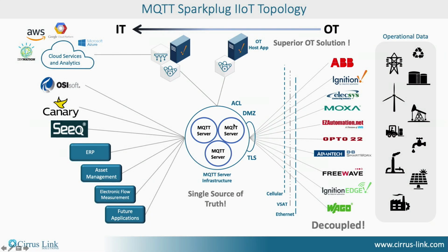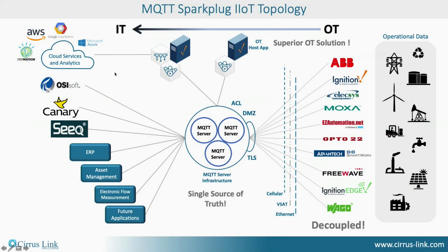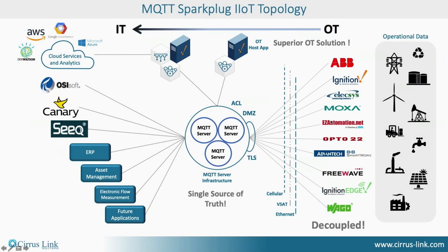You don't care, well, you do care, but if your HART transmitter dies, the edge of network device is there to tell you that it died. That's not a problem. The problem is when your edge of network falls off, then consuming applications that are subscribed to that death certificate can take corrective action, knowing that, say, my entire Opto22 device fell offline. Now everything coming from that device is stale, it's last known good.